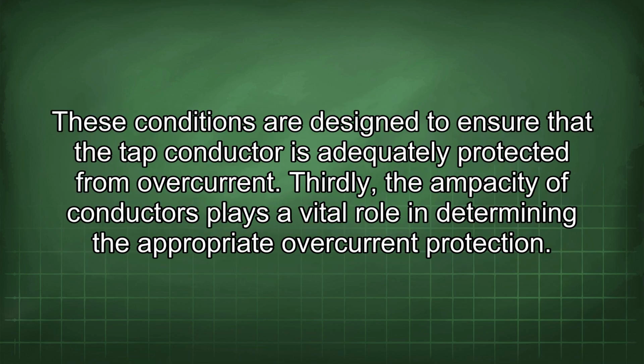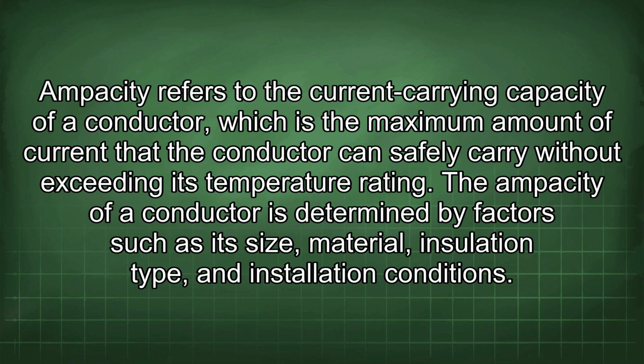These conditions are designed to ensure that the tap conductor is adequately protected from overcurrent. Thirdly, the ampacity of conductors plays a vital role in determining the appropriate overcurrent protection. Ampacity refers to the current carrying capacity of a conductor, which is the maximum amount of current that the conductor can safely carry without exceeding its temperature rating. The ampacity of a conductor is determined by factors such as its size, material, insulation type, and installation conditions.